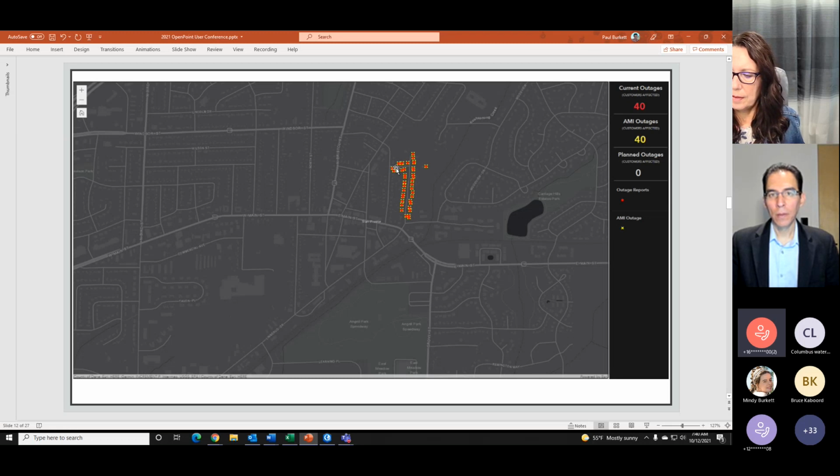And now, working on a report with that, we've set it up so that you can export the outage events that you need into a spreadsheet, a CSV file, and then the APPA eReliability website has an import feature where you can import those directly, and that's where we keep track of our statistics for the year for reporting. So we get an accurate time when the meters went off and when they came back on. There's no guesswork involved anymore, trying to remember. And we also get an accurate number of customers. Before, there was some guesswork involved there.